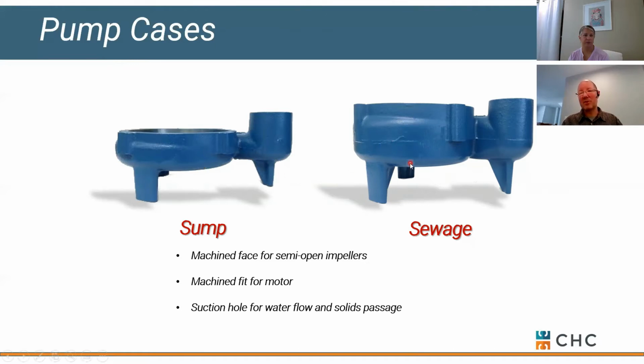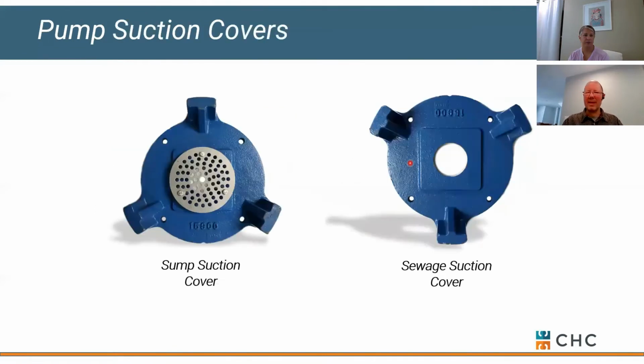So sewage applications, you'll have a much taller case, meaning a much taller impeller, more potential to pass large solids. So maybe from a quick submittal review, just by looking at the case, you can say, hey, this is probably a clean water pump versus something designed for solids. The other thing that might be unique is if you have a clean water pump, there tends to be a strainer on the bottom of it, limiting the max particle size that is going to enter the case or ultimately your impeller. Where sewage is wide open, looking to pick up any debris that's in your sump.